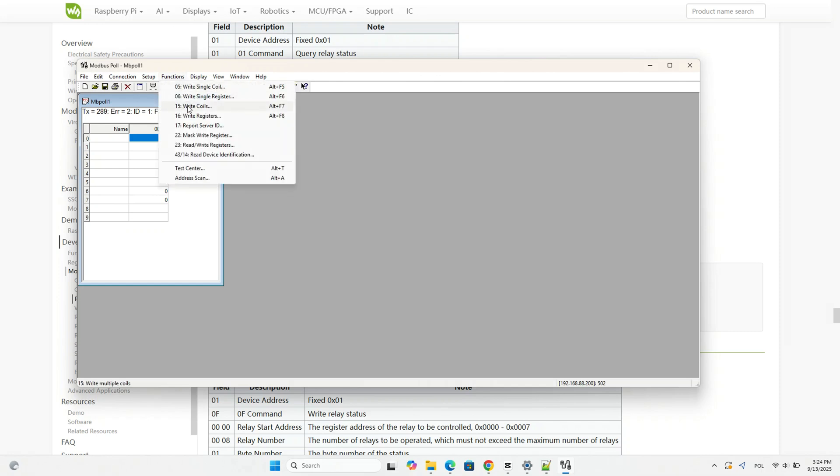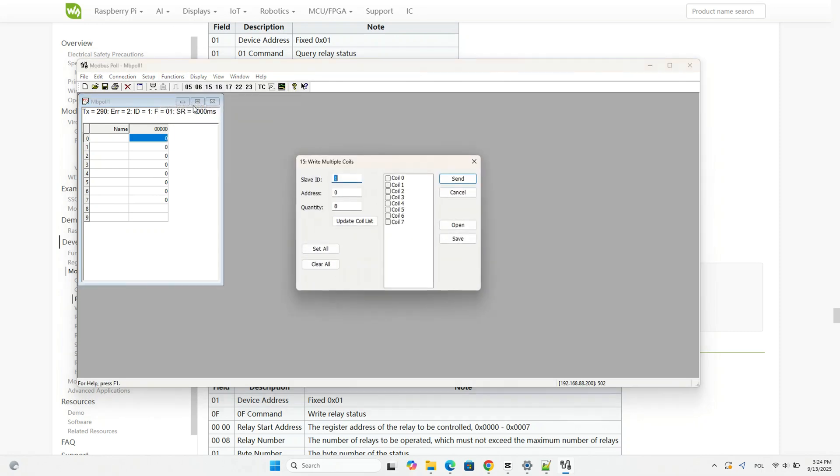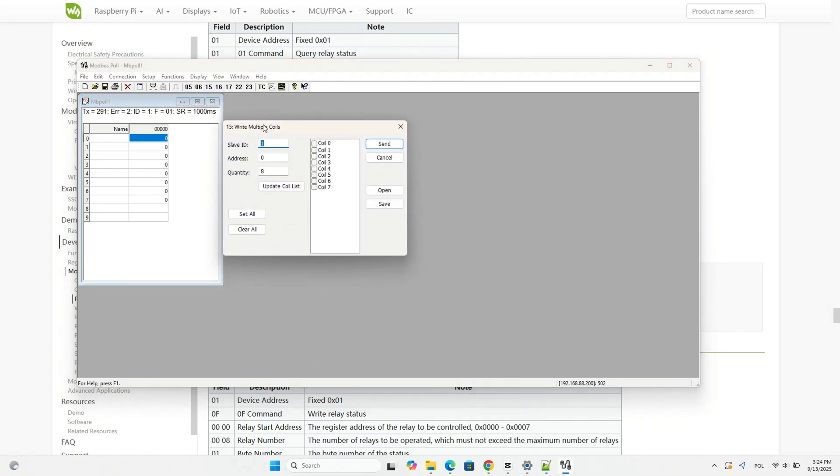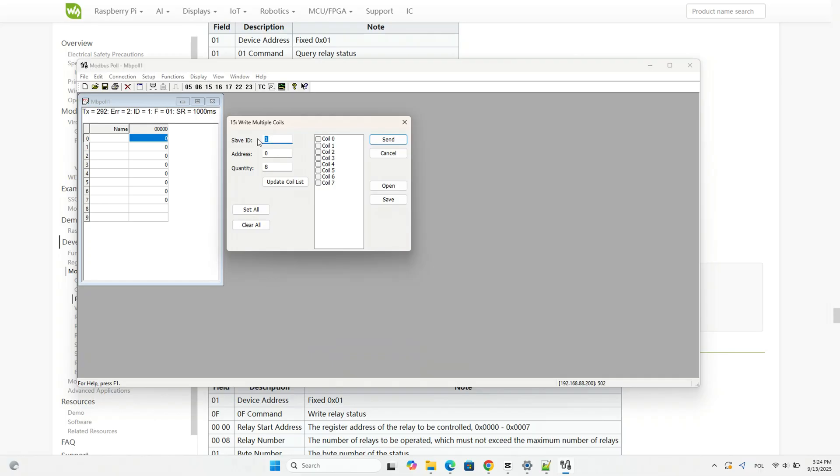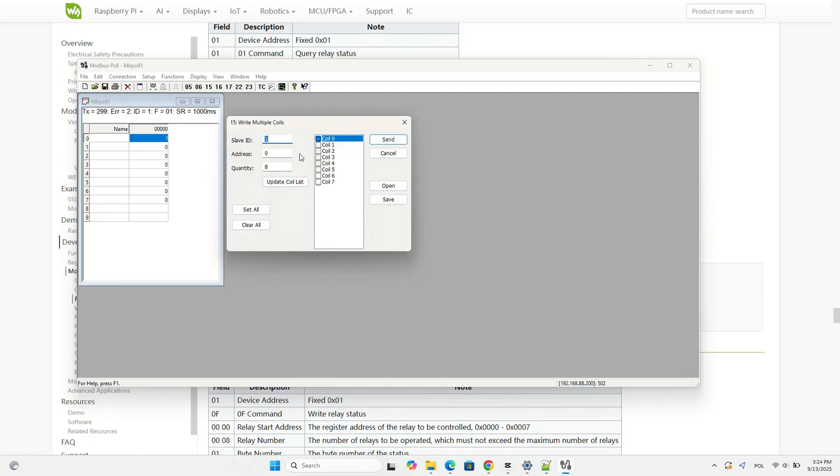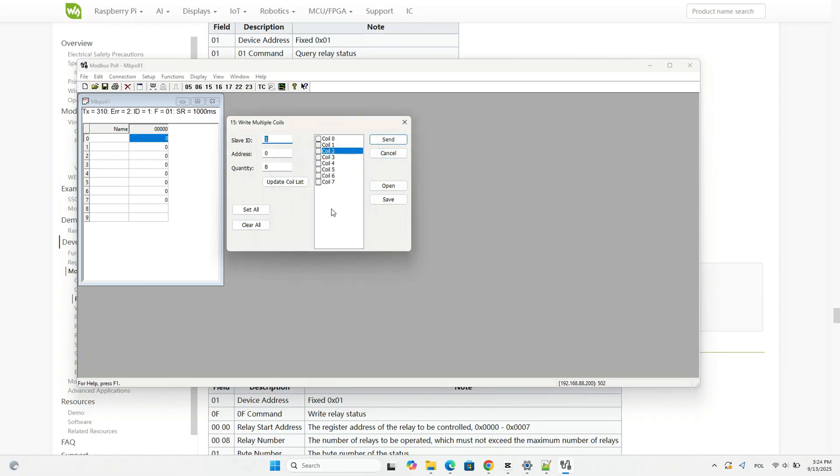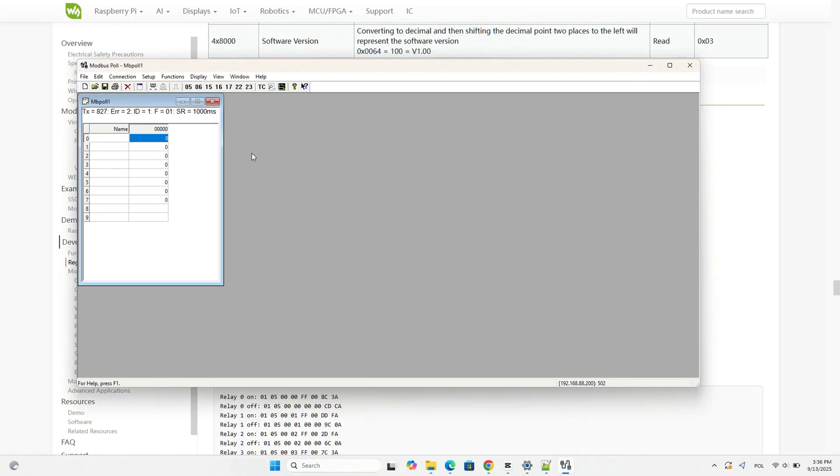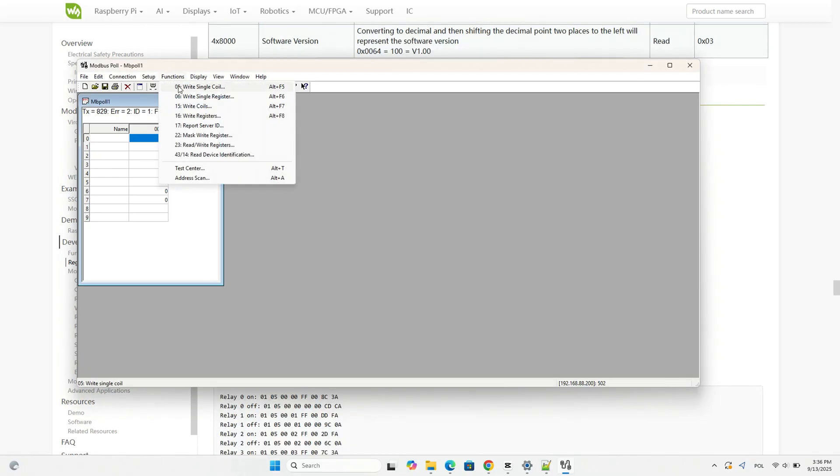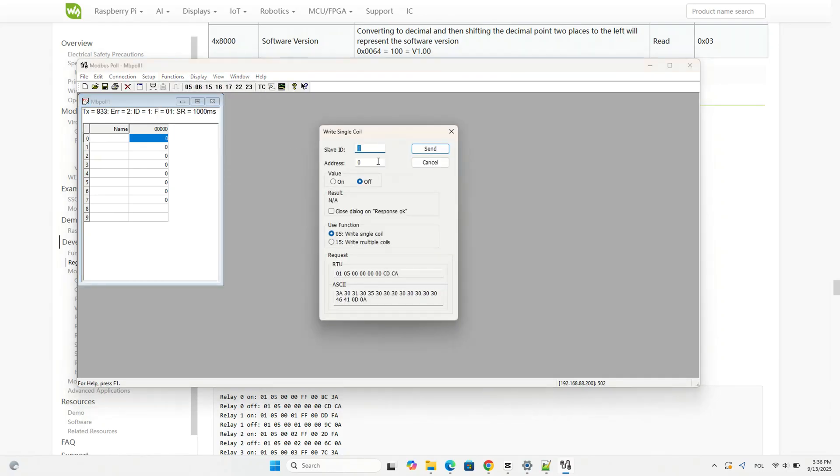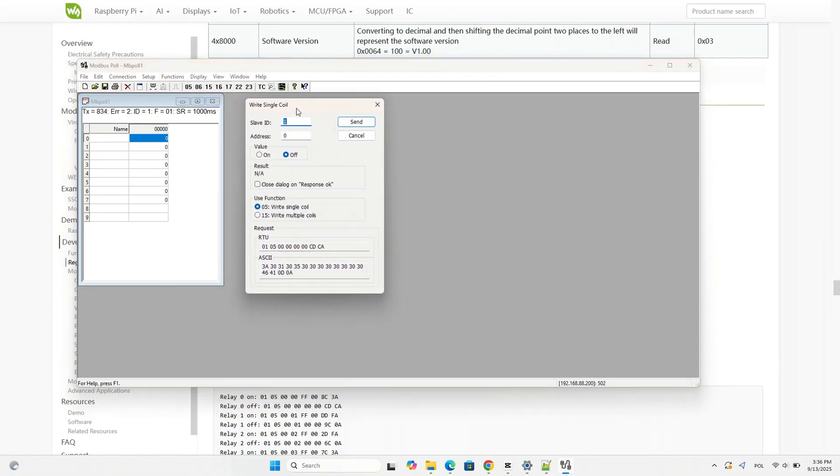Next, go to the function menu to control the relays and select function 15, write coils. In the newly opened window, toggle the relay and on the left you can see that its status has changed to active. Another Modbus function that allows you to trigger a single relay individually is the write single coil function, which has the number 5.